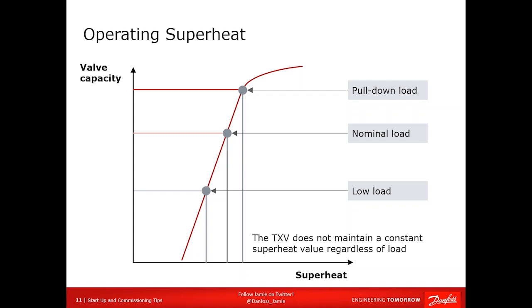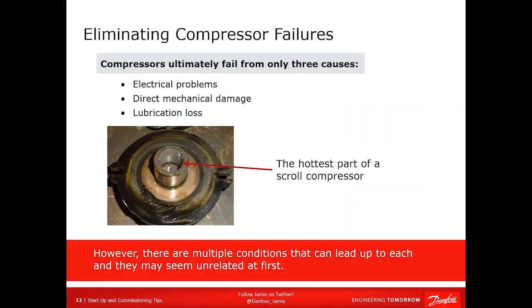So the difference between superheat at low load and high load is called opening superheat. So if you notice high superheat, but you also have high evaporator temperatures, high evaporator saturation temperature, that is nominal. All right, they go hand in hand. If you notice low superheat and low evaporator temperatures, that just means you have no load on the evaporator. The superheat indicates how much refrigerant is in the evaporator compared to the load. As your load increases compared to refrigerant volume, superheat goes up.